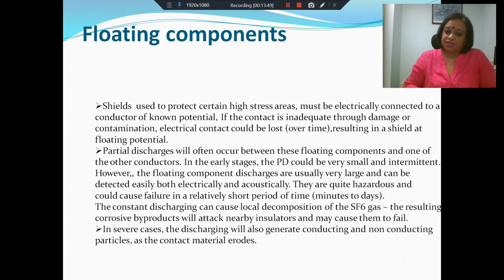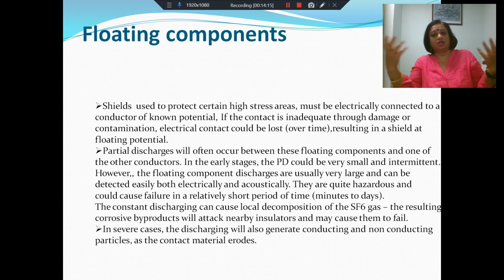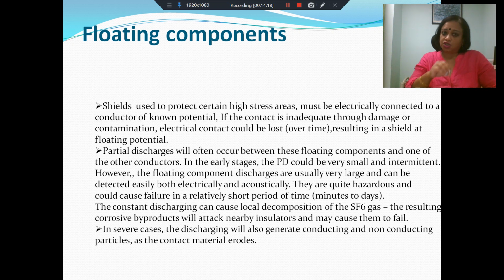In severe cases, discharging will also cause more metallic particles to be generated. So there will be some kind of erosion or bombardment, and as a result, your metallic contacts may actually crumble, and they may produce a lot of powdery substance. These metallic particles then in their turn will continue to produce discharge and hopping excursions, and they will acquire charge and cause partial discharge. So this is one PD that we can quite well control.